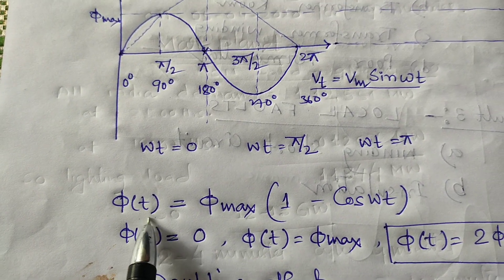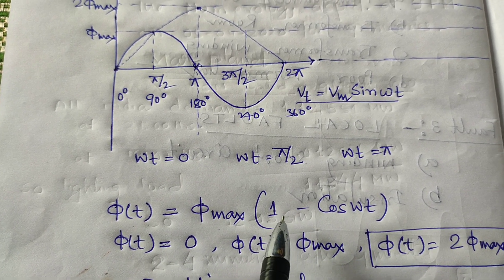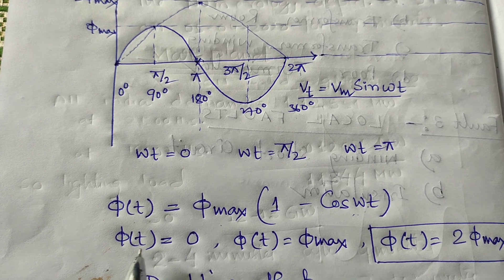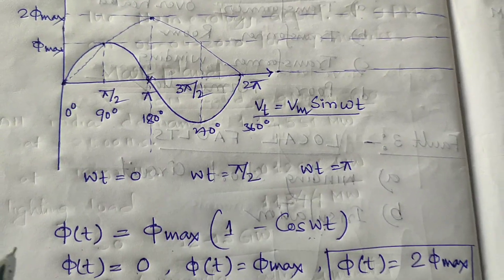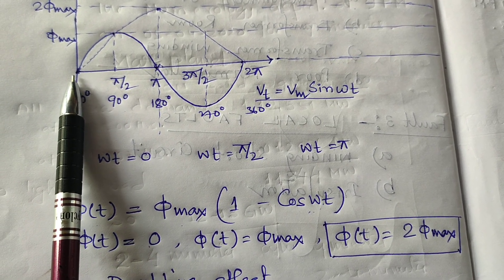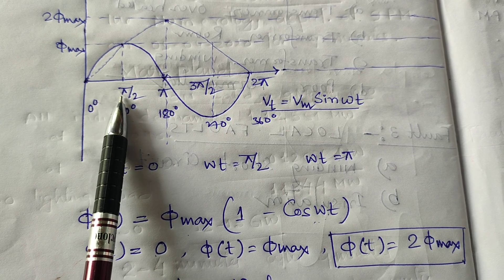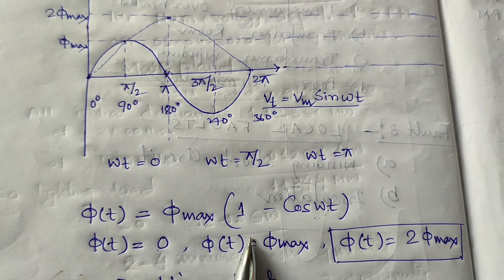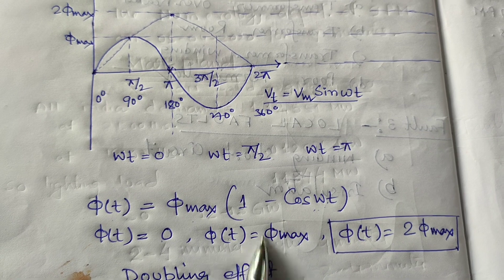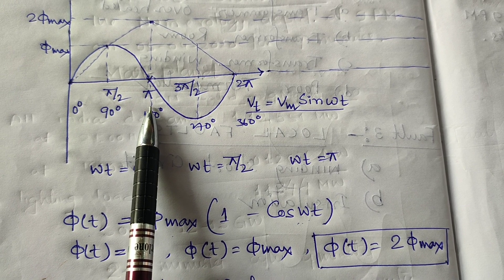At 180° (π), if we consider φ(t) = φmax(1 − cosωt), substituting t = 0 gives cos(0) = 1, so φ(t) = 0 — the flux is zero at the initial position because the transformer is not yet charged. At 90° (π/2), cos(90°) = 0, so we get the maximum flux φmax. When we reach 180° (π), we obtain the maximum value of two times the maximum flux.